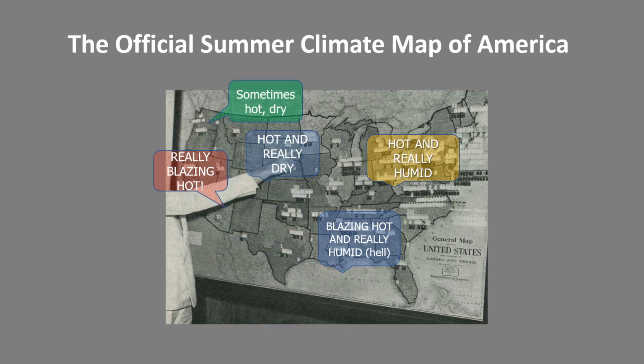And up here in the northwest, we sometimes get hot. Compared to the rest of the country, we're still pretty mild, but we do get hot, and air conditioning is becoming more and more popular, especially as we run into the 5th season, which is the smoke season. People are reluctant to open their windows and will rely on mechanical cooling systems. The good news is when we do get hot, we get dry. All we have to worry about is the sensible capacity of the air conditioner and not the latent capacity.